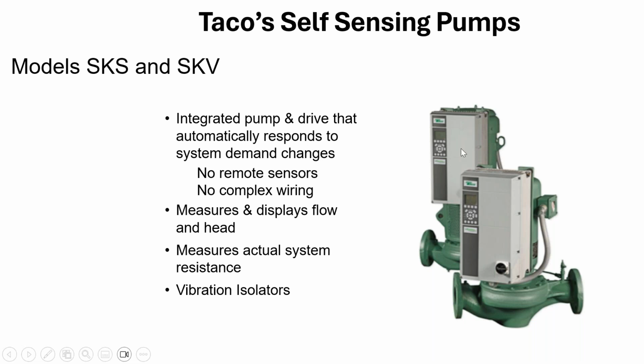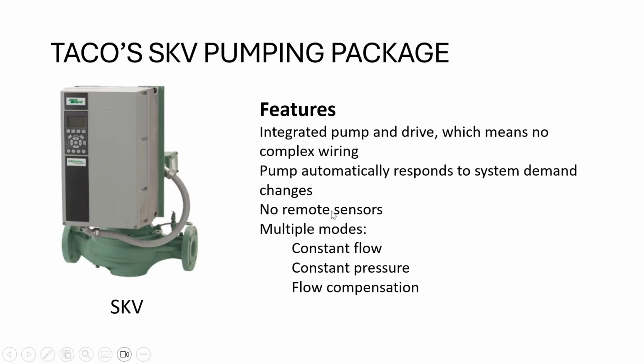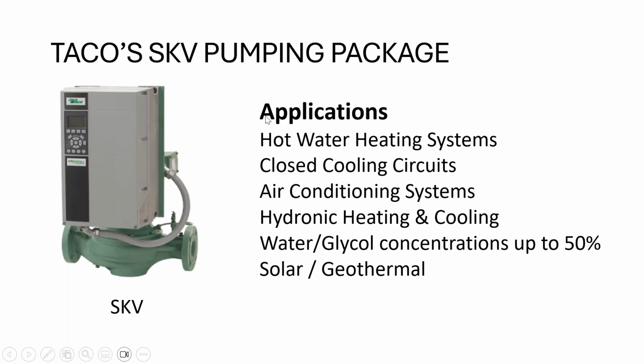And by the way, you can mount these remotely on a project as well, right? It's just wiring and mounting it. So if for whatever reason it needed to be mounted on the wall or something like that, that can be done as well. Constant flow, constant pressure, automatic response to system demand changes. No remote sensors. I can't emphasize that enough. No remote sensors.